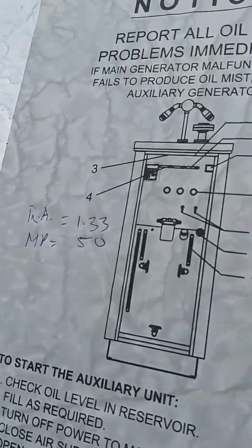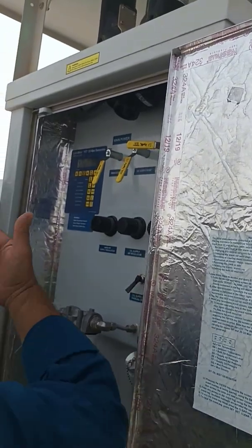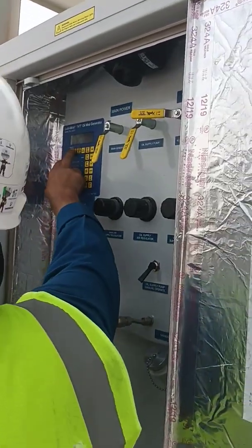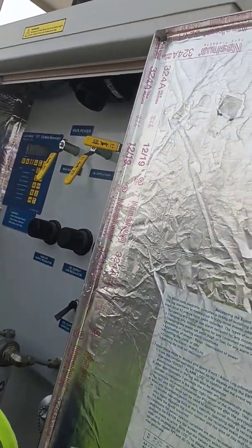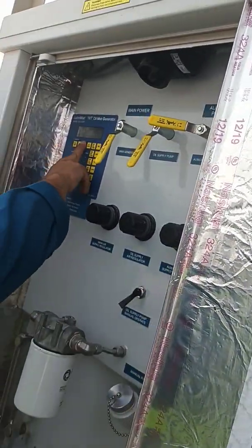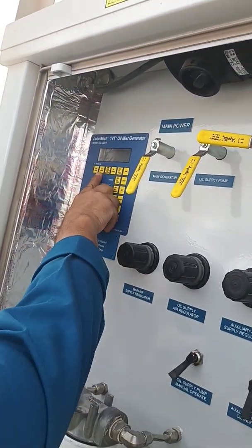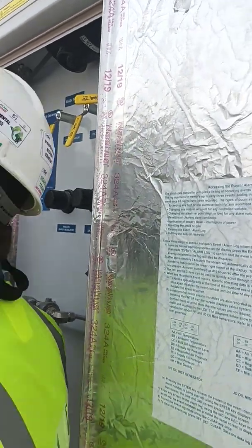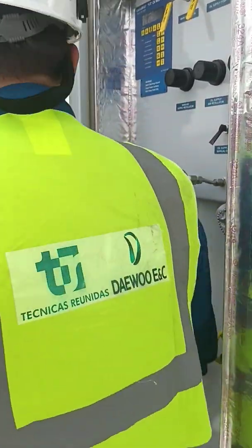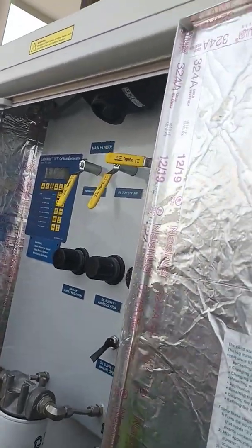I don't care what the air temperature is because it's 49 degrees always, and you can have it in the manual that it is set to 49. Oil temperature, remember we don't have an oil heater. Oil temperature is going to be pretty much the same as the ambient temperature. Ambient temperature now is 41. The oil temperature is only 35 because in the night it comes down to about 26 degrees. So it's still not heating up, but it's normally about the ambient temperature. Now it's about 35, that's okay.